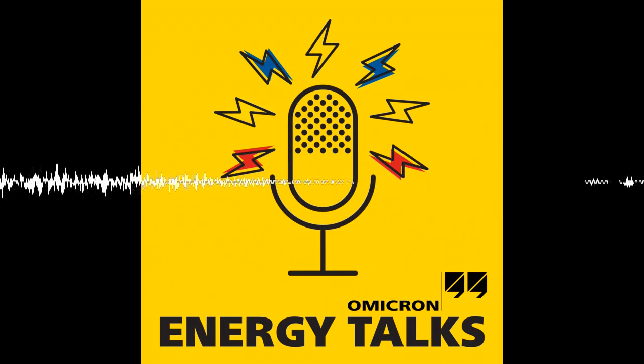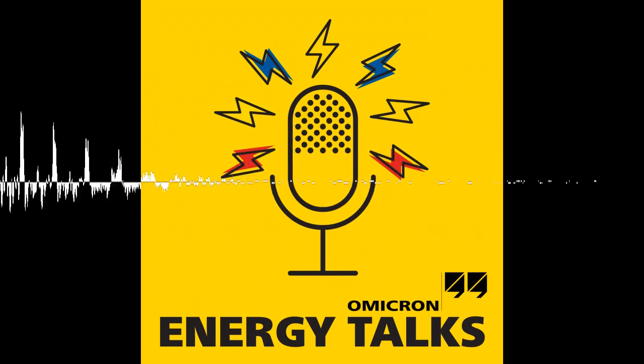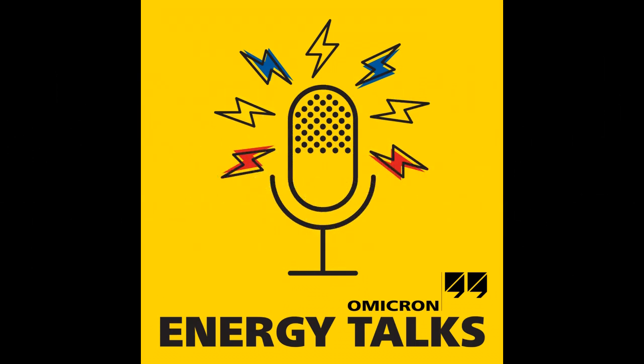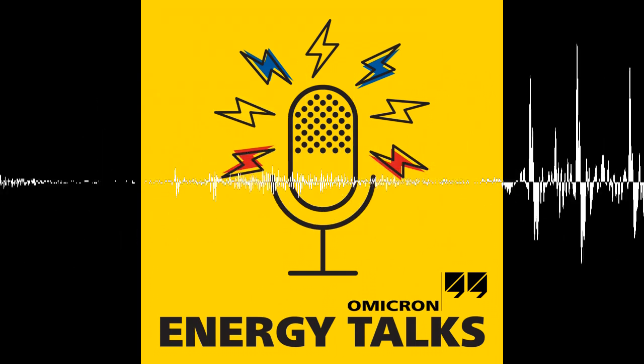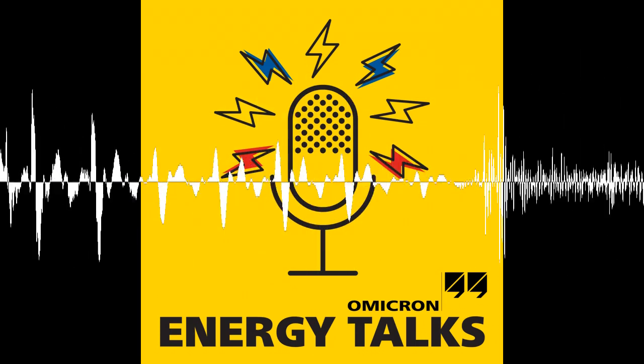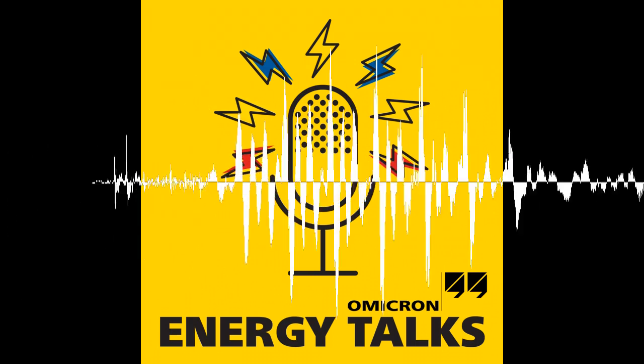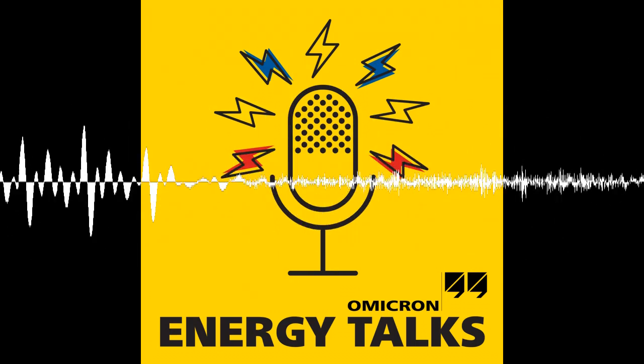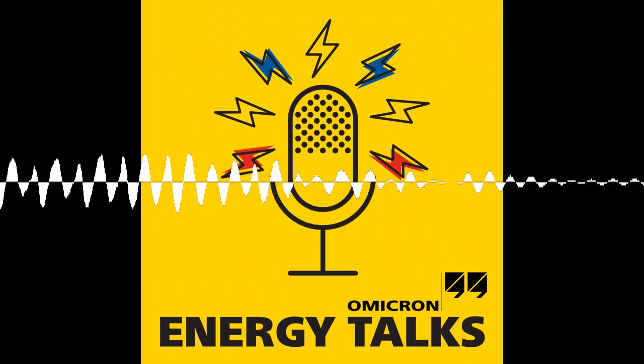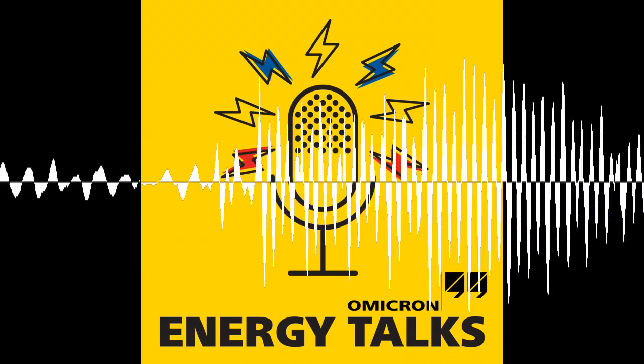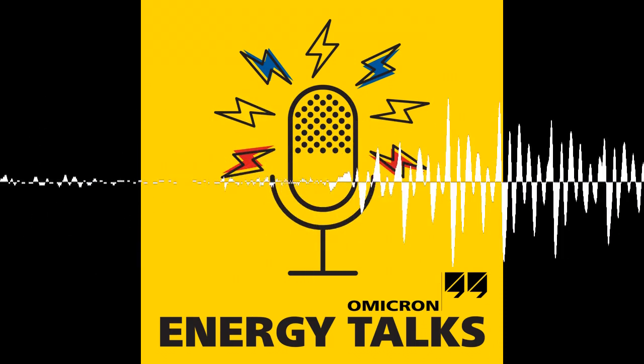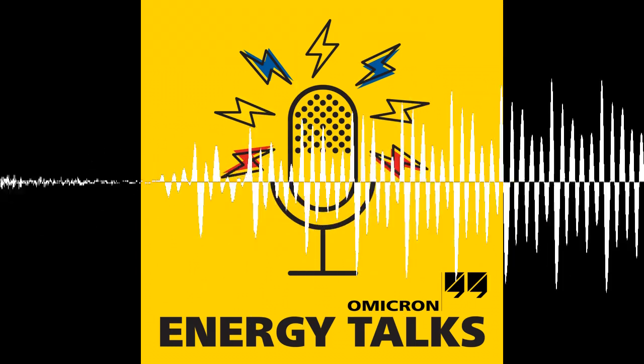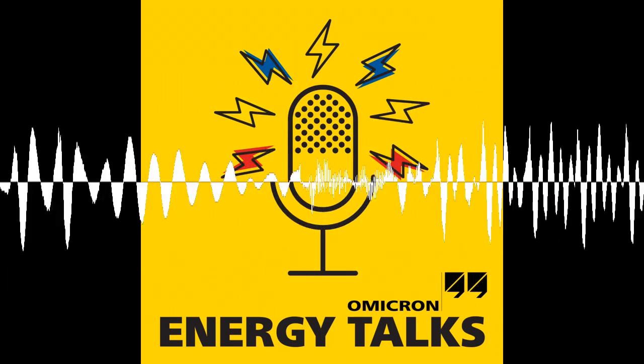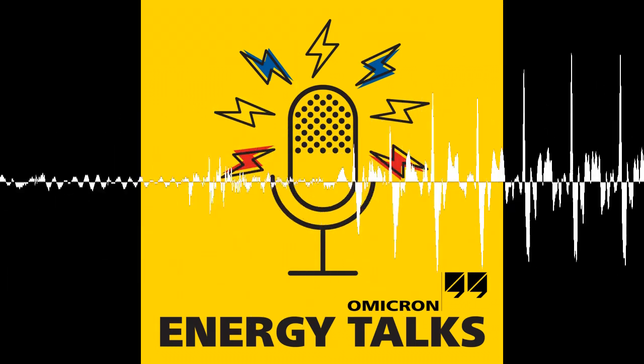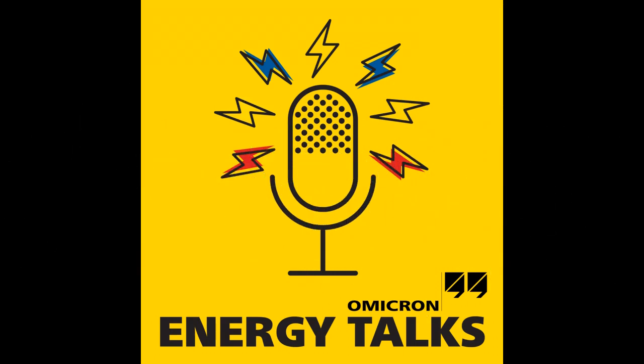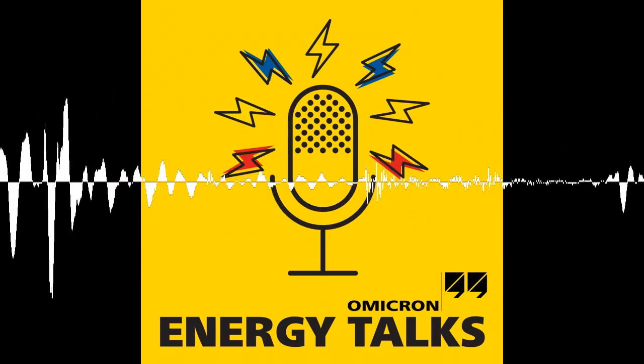Well, thank you, Alex. Christoph, I would like to ask you a few questions. First of all, how is partial discharge testing generally performed on transformers in wind parks? Is it different than transformers in substations? Well, it depends. The very first thing you need is a proper HV source, a high voltage source, to generate the test voltage for the PD test. Okay, so we're talking offline testing then. Right, most of the time it will be offline testing.